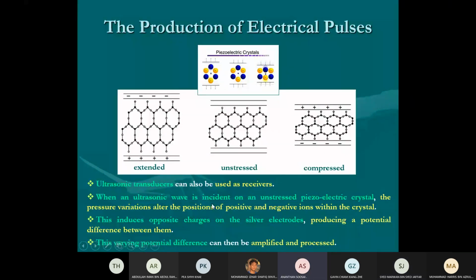Look at the second point. When the ultrasonic waves are incident on the piezoelectric crystal, the pressure variation alters the position of the ions. This induces opposite charge on the silver electrodes, producing a potential difference. This varying potential difference can be amplified and processed. The transducer alone cannot do it. The signal is very weak, so it needs to be sent to an op-amp to amplify it. So what type of op-amp do you use here, comparator or feedback? Use feedback, because the signal pattern we need to retain but enlarged.